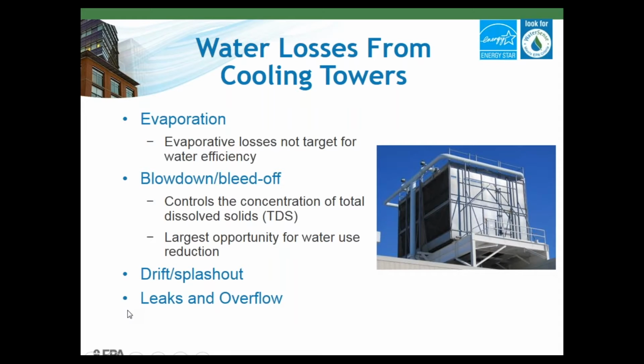All cooling towers have a discharge water stream referred to as either blow down or bleed off. We'll call it blow down here. The reason for the blowdown is to keep minerals and dissolved solids from building up in the water circulated through the tower. The makeup water supplied to the tower contains dissolved solids. As water evaporates, these solids that stay in the circulation begin to get concentrated over time. If the concentrations get too high, the solids will begin to form scale on the surfaces of the chiller system, which can degrade performance or damage equipment. Therefore, some water is regularly discharged or blown down to keep these dissolved solids in check.